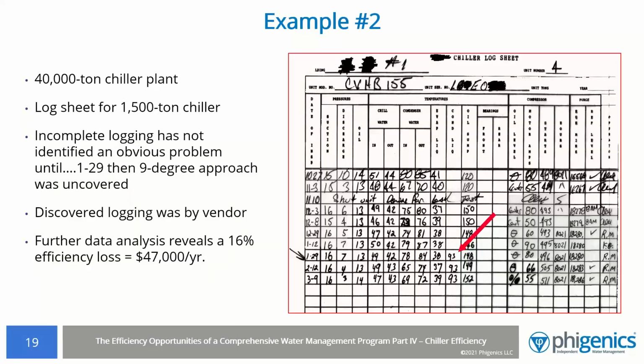This is a slide from a chiller plant in a large facility that had a total of about 40,000 tons. This is a log sheet for a 1,500-ton chiller. And again, if you look at the log sheet, you can see that it's logged every week or so, every 5, 7, or 8 days. They've got a fair amount of data. They don't have it down to a 1/10 of a degree, but they got round numbers in there.